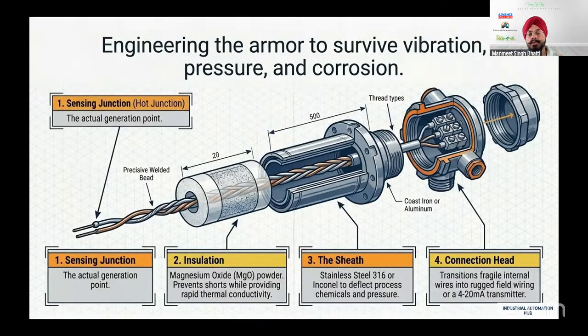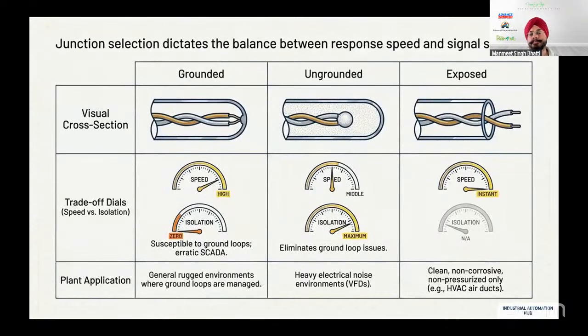I have given you a breakup on this. Now, these are the 3 charts where you will find how the response speed is going to be based on the design part. So if you see the first part, the sensor is actually grounded. Grounded means the sensor is actually touching the body. So on the left side, first left column, as you see, the sensor is showing grounded. Grounded means it's touching the body.